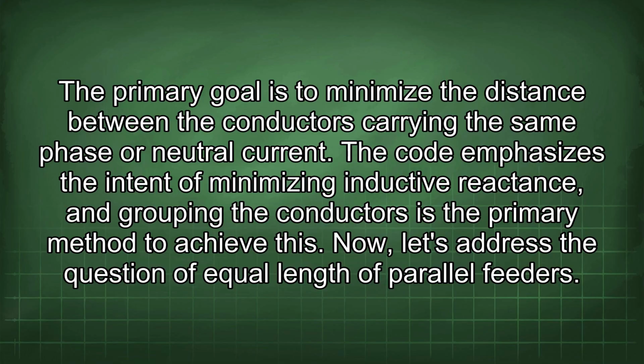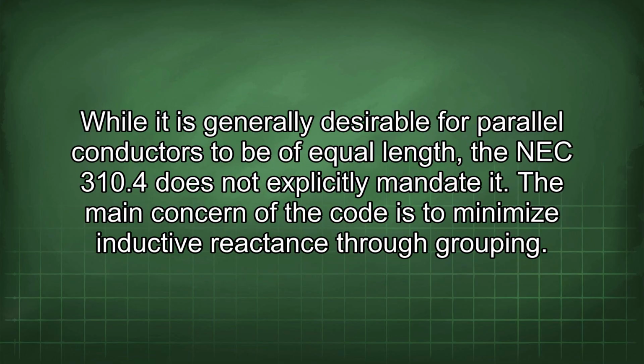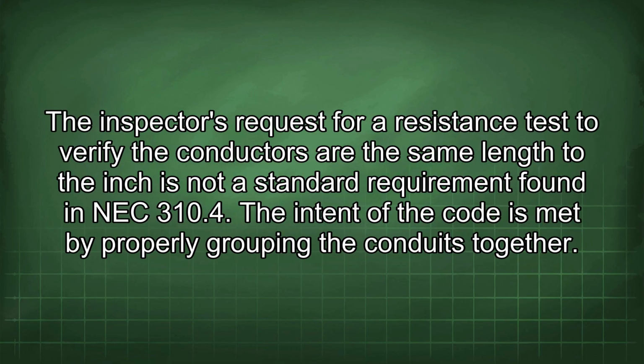Now, let's address the question of equal length of parallel feeders. While it is generally desirable for parallel conductors to be of equal length, NEC 310.4 does not explicitly mandate it. The main concern of the code is to minimize inductive reactance through grouping. The inspector's request for a resistance test to verify the conductors are the same length to the inch is not a standard requirement found in NEC 310.4. The intent of the code is met by properly grouping the conduits together.